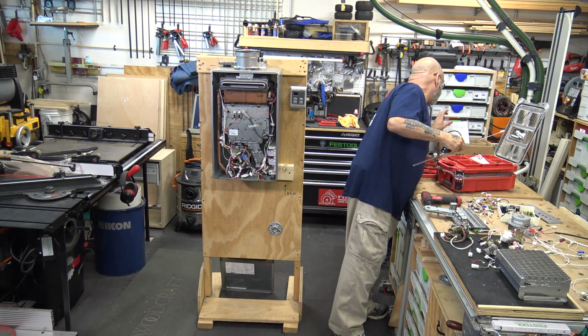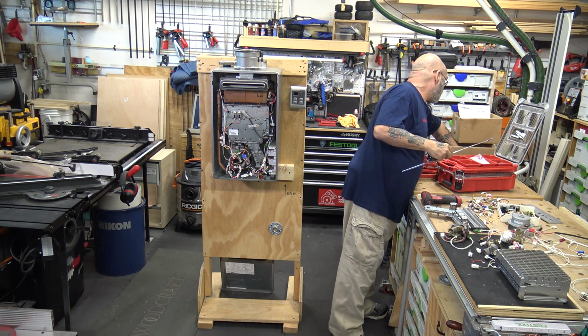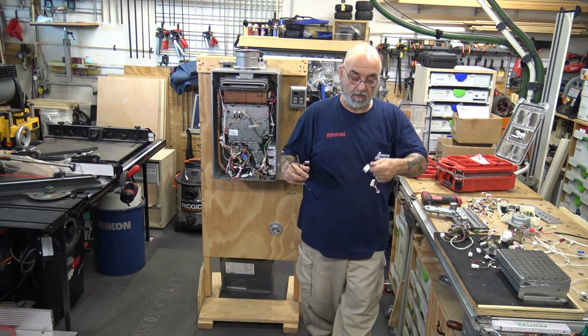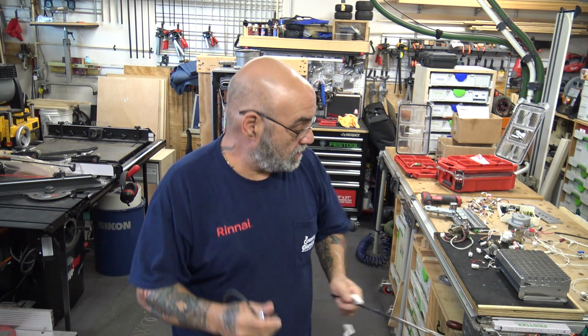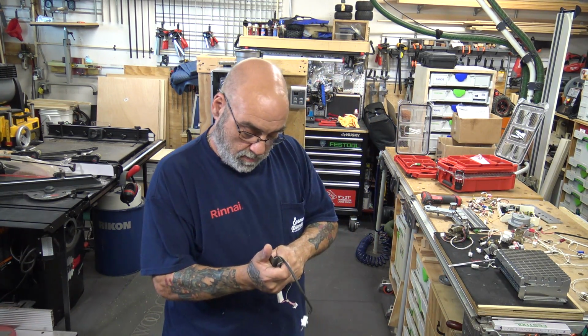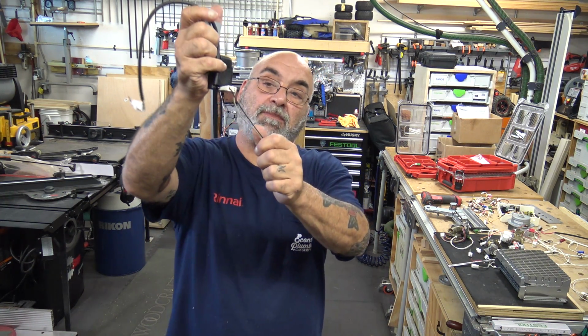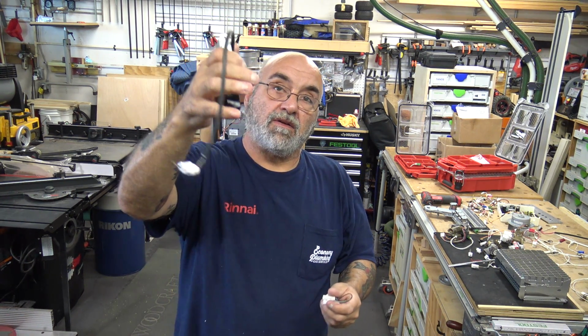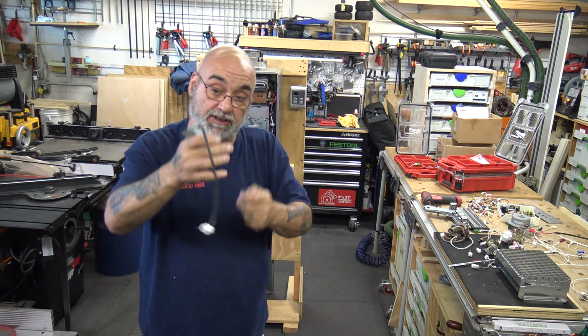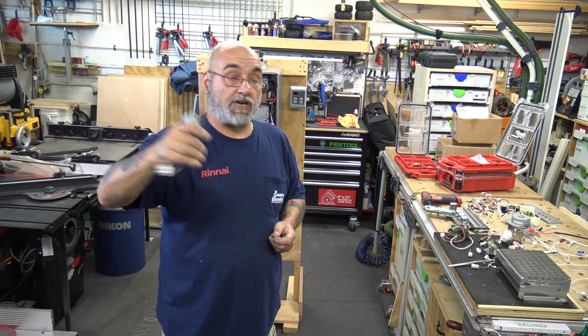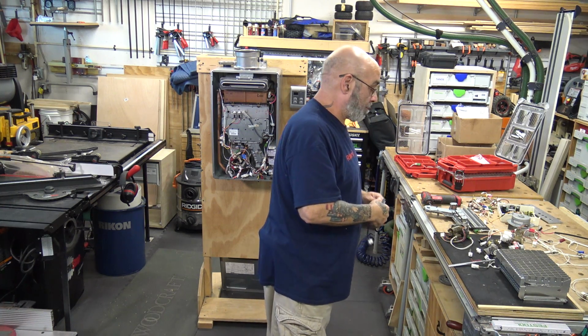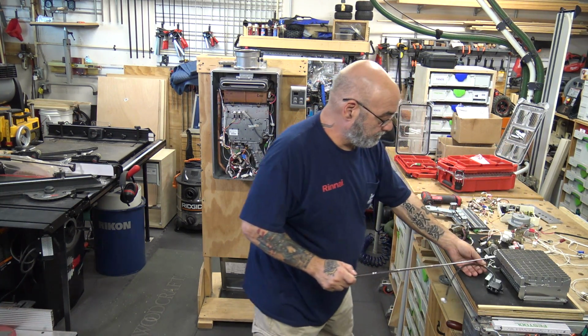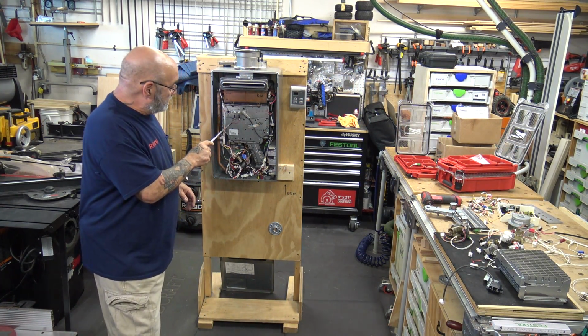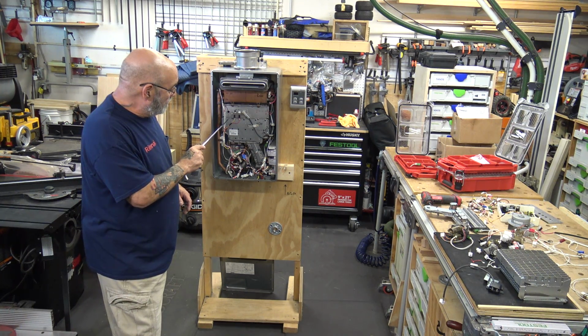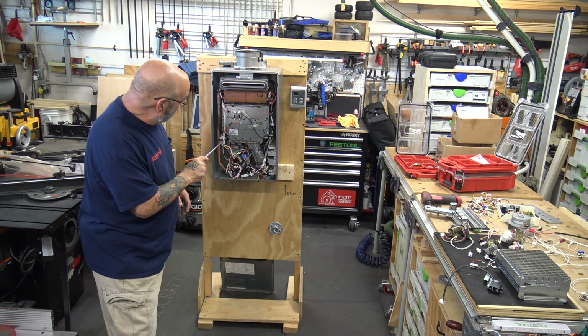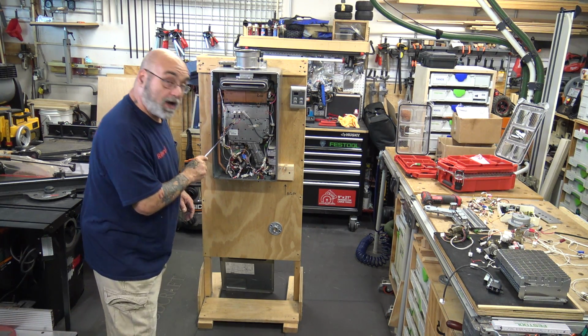the plug, see, by releasing the plug, so once you pull it out, now you release the plug, your igniter is out, you can now change it. Okay. Then, as the burner is firing, you have 2 flame sensors. You have a red one and you have a yellow one.